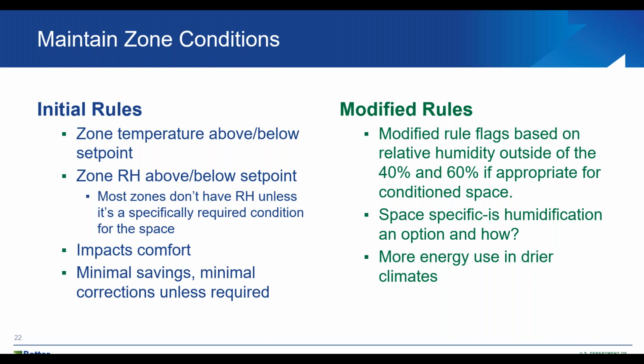Well, under COVID, you may have to modify these rules or add new ones. In a lot of cases, the spaces actually do not have humidifiers in them. So the question becomes, are you going to add humidifiers to them? And the ones that do have them, typically the overriding factor is going to be based on the space conditions. Like I said, a library, an operating room, or pharmaceutical, which requires certain space conditions. In a drier climate, if under COVID you're adding more humidification, this could be a significant energy user as well. And next slide, please.